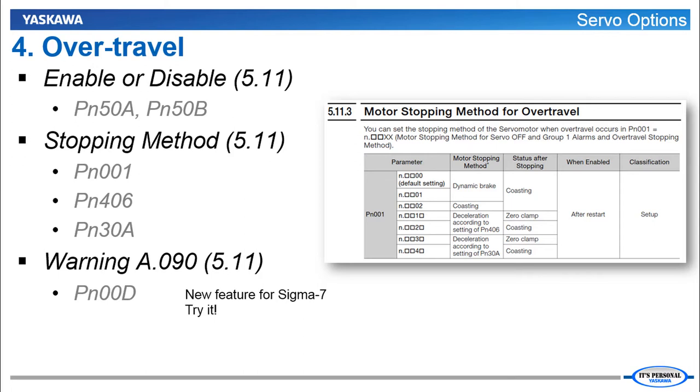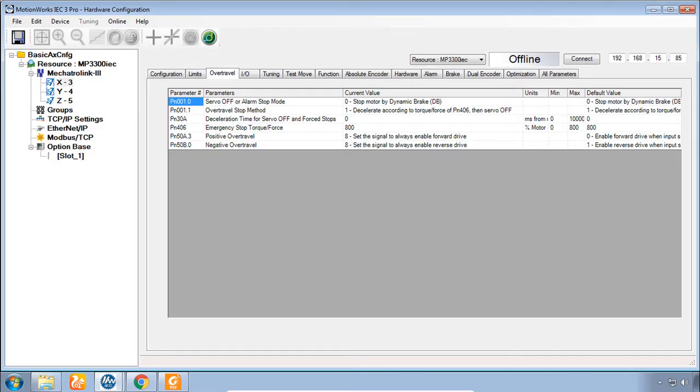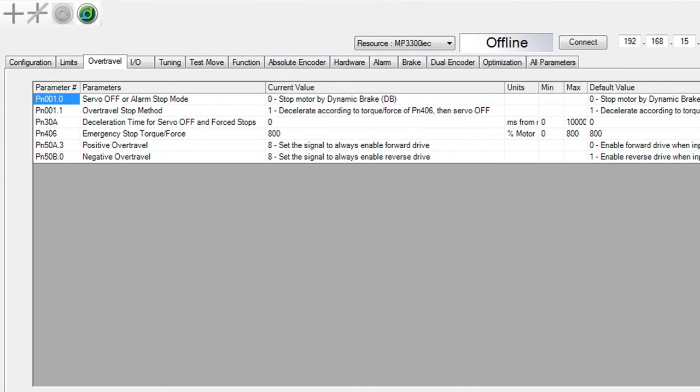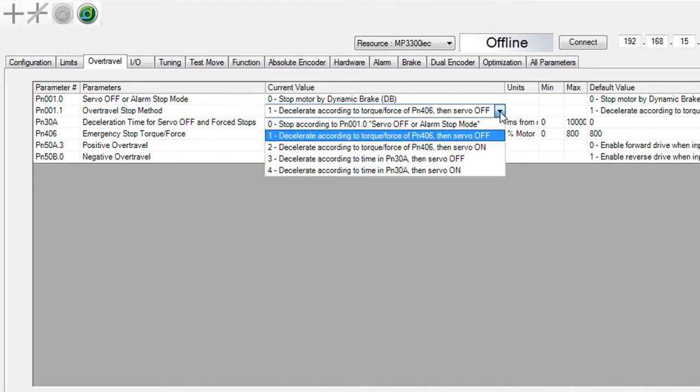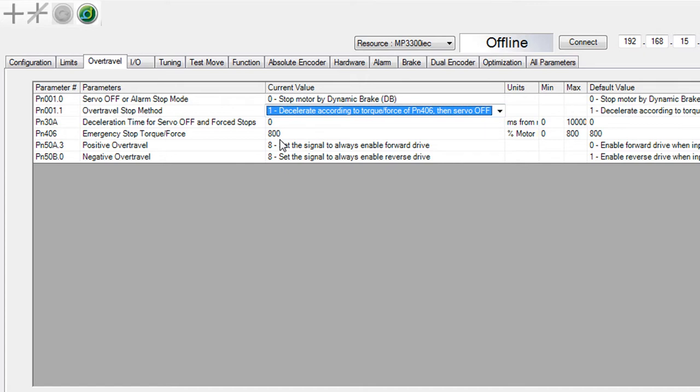And new here in Sigma 7 you can have a warning appear in the amplifier. In MotionWorks IEC hardware configuration. Most of these are in the over travel tab. Of course in the previous video we had you guys set these to off to enable the forward direction. But also in this list is the emergency stop torque force. And you can choose to have the motor stop that way. That is the default here. Stop with the torque set in this parameter.